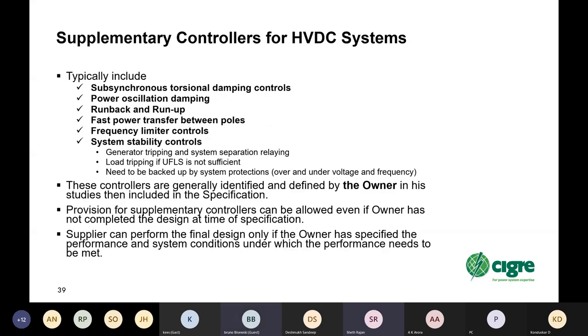So supplementary controllers for HVDC systems typically include subsynchronous torsional interaction damping controls, power oscillation damping, run back and run up, fast power transfer between poles, frequency limiter controls, system stability controls, which can include generator tripping and system separation relaying, load tripping if the under frequency load shedding is not sufficient, and any system stability controls need to be backed up by system protections, which can include over and under voltage and frequency protections.